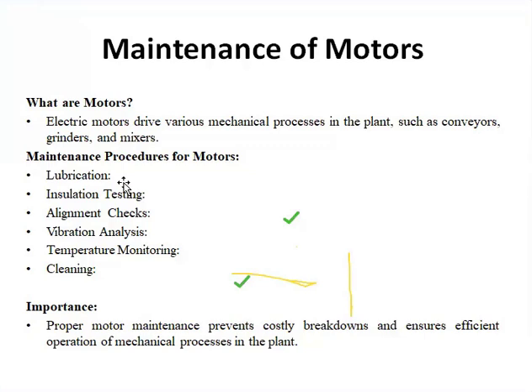Then insulation testing, use of the insulation tester, comes into place here to ensure that the motor windings are not compromised. For instance, a drop in insulation resistance could indicate moisture that has been created in the motor winding, leading to a short circuit. So if the insulation of the motor comes down, that means there is some moisture that has been created either in the primary winding or secondary, or in the stator or rotor, that will create a short circuit in the long run.